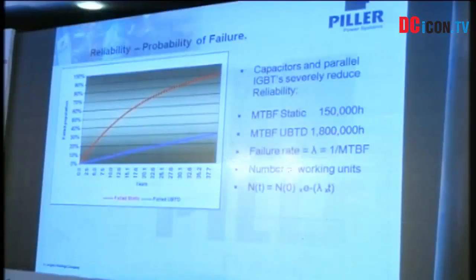So if you look at all of those parameters, for a static UPS the mean time between failure is roughly 150,000 hours. This could be a very good quality static UPS, and you have a reliability, or mean time between failure, of 150,000 hours. Whereas the MTBF for a rotary UPS is 1.8 million hours. 1.8 million hours. There's a huge difference in the time between the failures because the components used are fewer. There are no static components, there are no switching components. So due to that, the reliability of these components is pretty high.